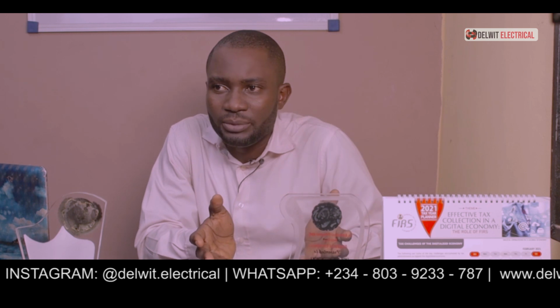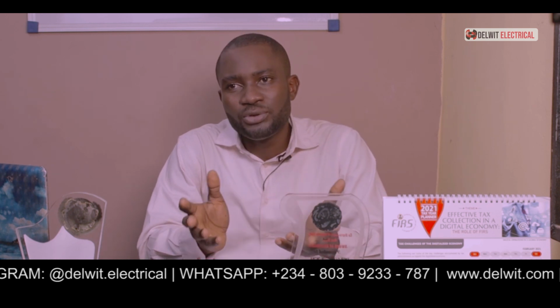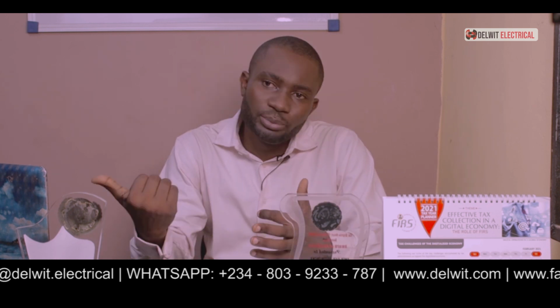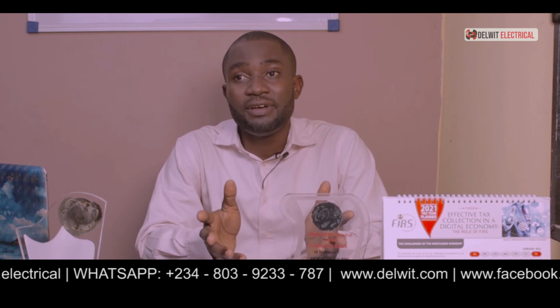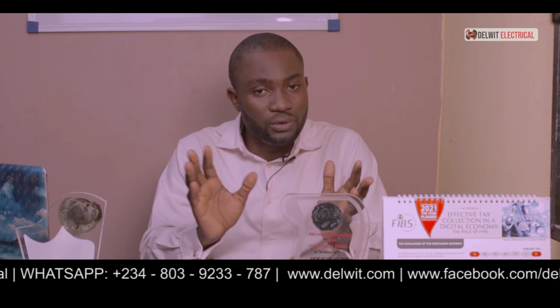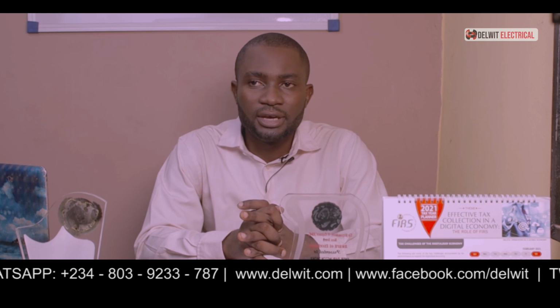Okay, the next one that is very prominent is the arc fault. Now you see some circuit breakers or some connection ports sparking. This might be as a result of loose screws or inferior circuit breakers, inferior 13-amp socket or the rest. So once you notice such, that could lead to the tripping of a circuit breaker. So it's advised you immediately change the screw or you change the entire circuit breaker.